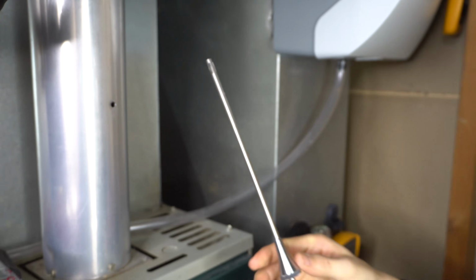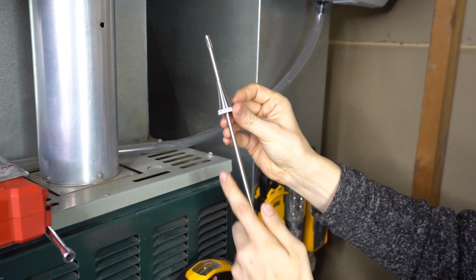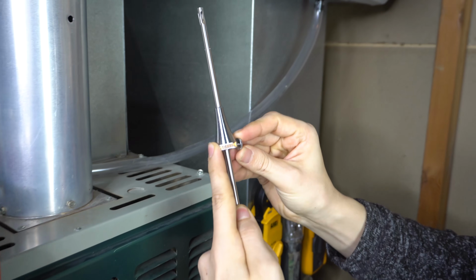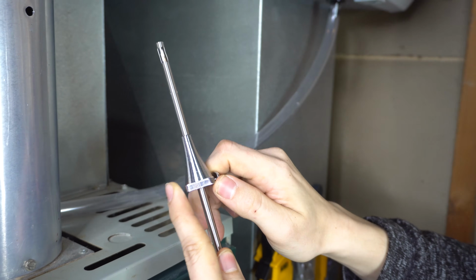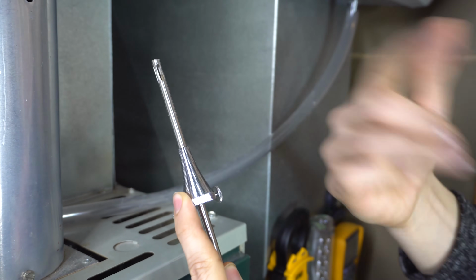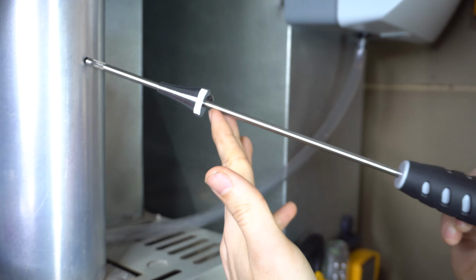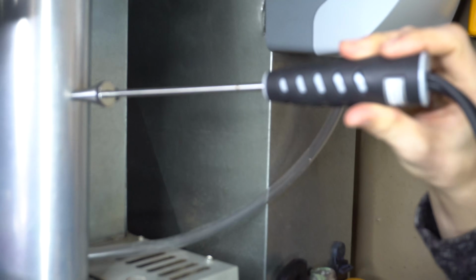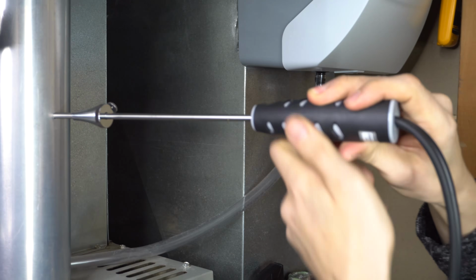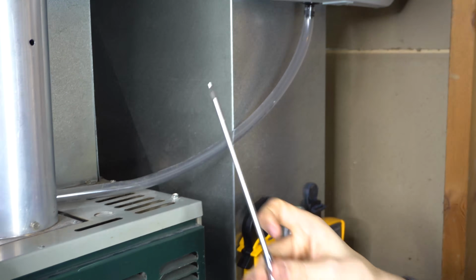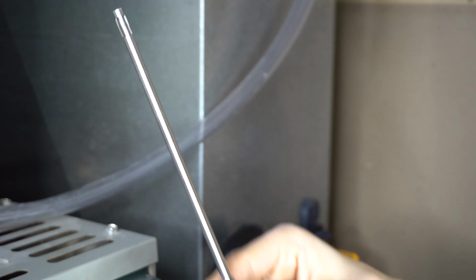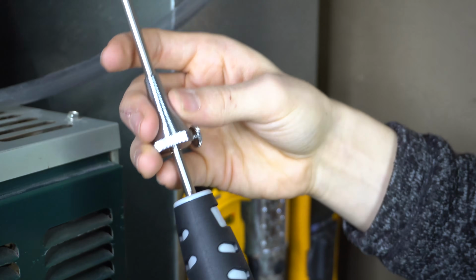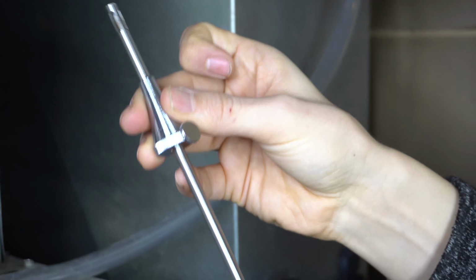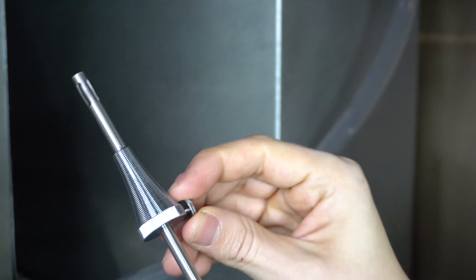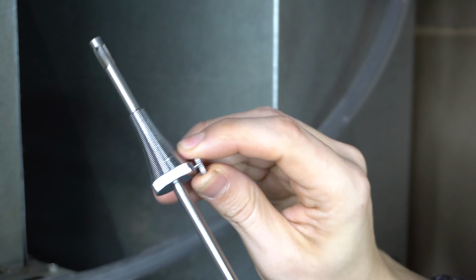And the purpose of this cone right here is so that you have a set measurement. So if you're doing furnace tune-ups all day long, you can just set this to a set measurement like right here. Or if you're taking it in and out, of course, it'll only go up to that cone right there. And what I like about this testing probe is that they made these little divots on the top and the bottom, which is really slick. It prevents this cone from falling off. So it prevents it from going too low, and it prevents it from going too high or falling off of the test probe. And of course you got the little tightening screw to set it in place.